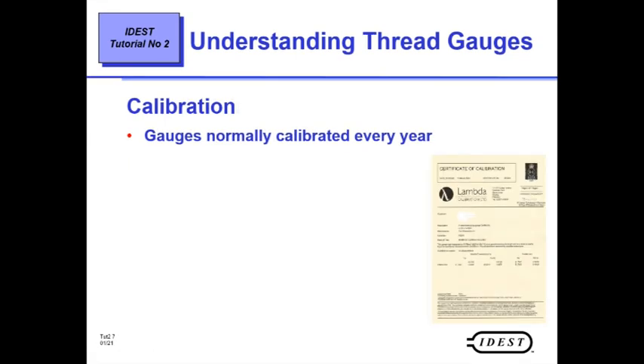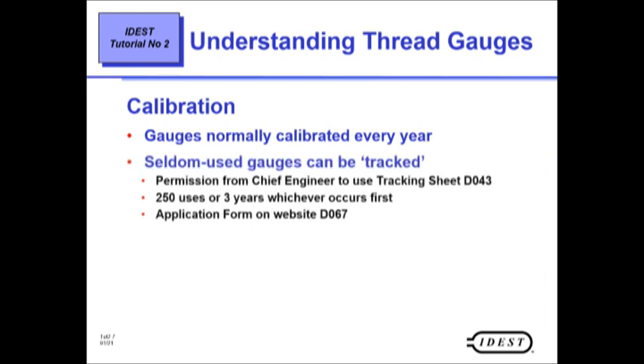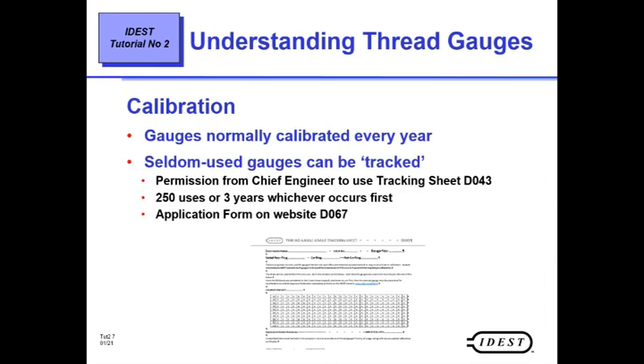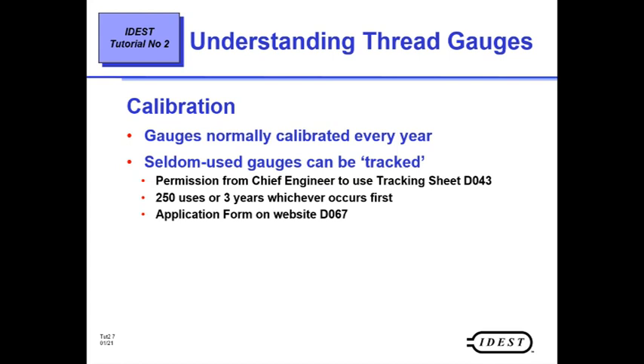And finally, on the subject of calibration, the gauges are normally calibrated every year. However, from time to time there may be gauges that you don't use very often, in which case the calibration can be extended by using a tracker sheet. You need to apply to the chief engineer using the application form D067 to get permission to use the tracker sheets. These would then be sent to you by the chief engineer. You can extend the life of your gauges to 250 uses or 3 years, whichever occurs first.